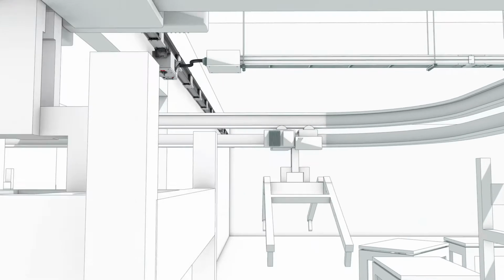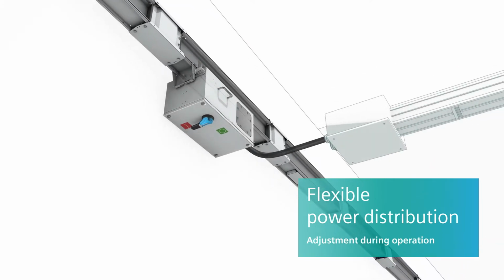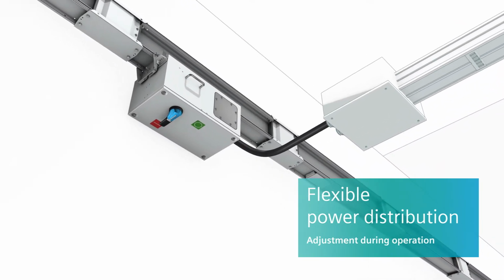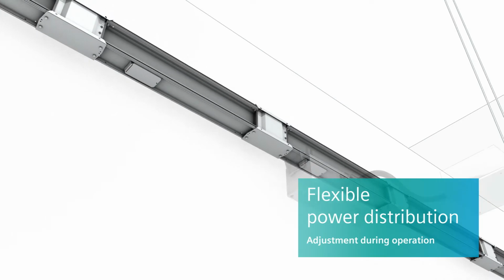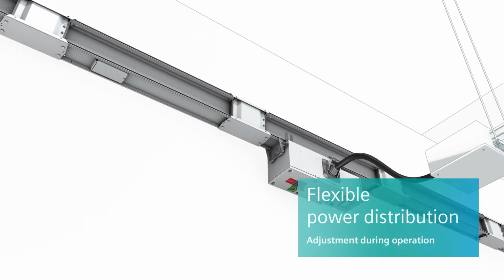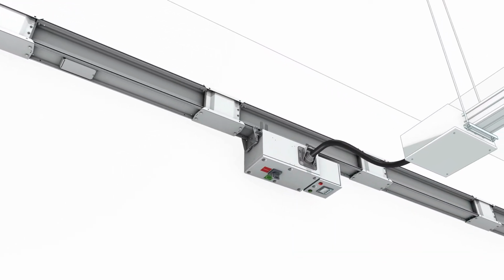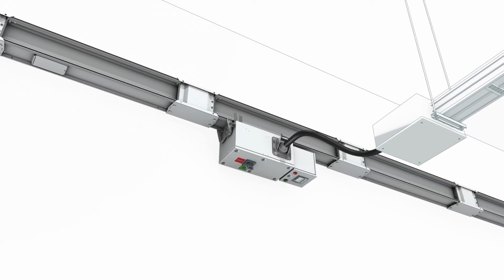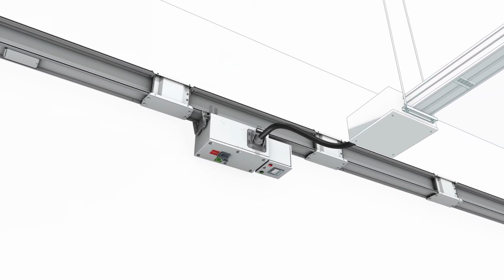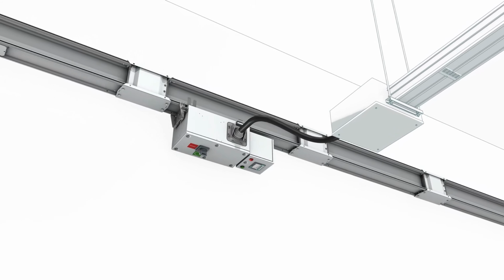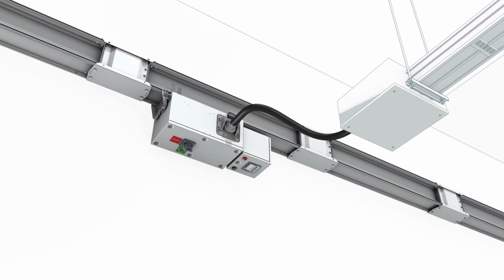And if you renovate or expand your plant at some point, the busbar trunking system will pull out its best trump card. It can be flexibly adapted during operation. You can equip the tap-off units with various switching devices and plug them into any tap-off points. That's how you can modify your power distribution system quickly and easily at any time. Can you say the same about a cable installation?